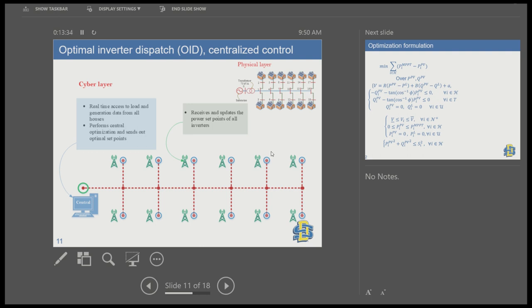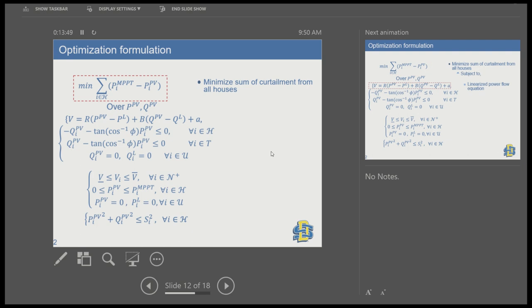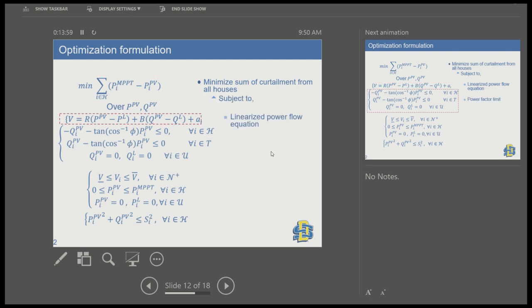The inverters receive those setpoints and then produce the amount of power specified. Mathematically, the optimization minimizes the sum of curtailment from all houses. We also have to meet power flow equations — the power input should equal power output at each node — and we use a linearized version of the power flow equations.